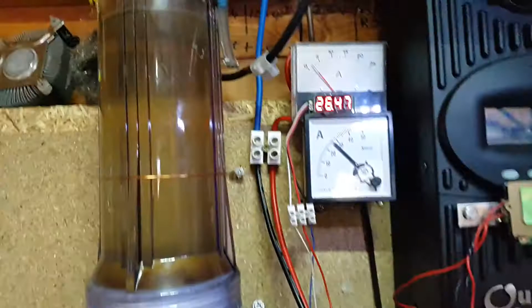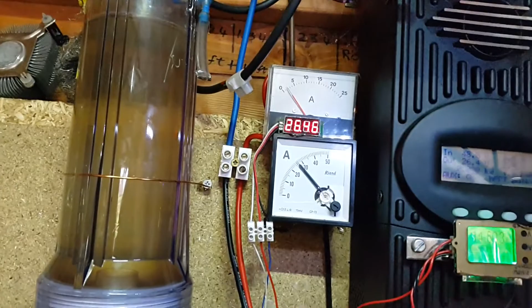I'll be having everything on a DIN rail, which is just a rail type for mounting circuit breakers, and also have a DIN rail mounted watt meter which will measure AC watt hours coming out of there, and that's so I can put it on the spreadsheet and keep track of how much energy I produce. What I'm going to do is wire this voltmeter directly to the battery, and what that will do is give me a more accurate reading of voltage drop.